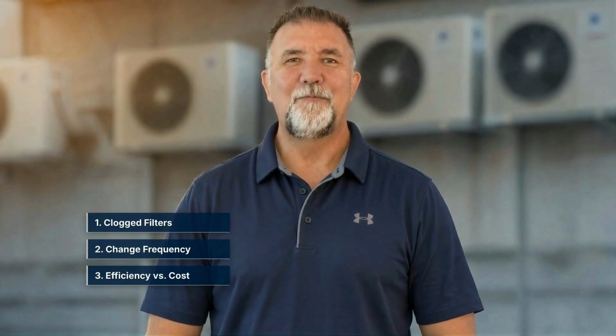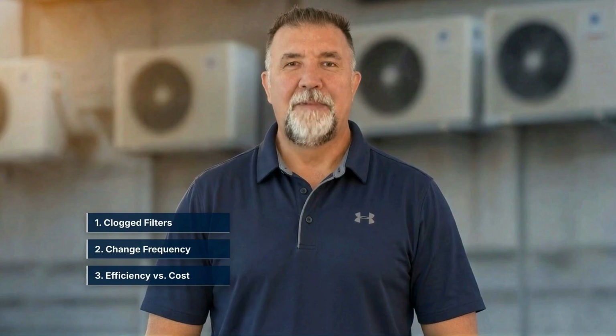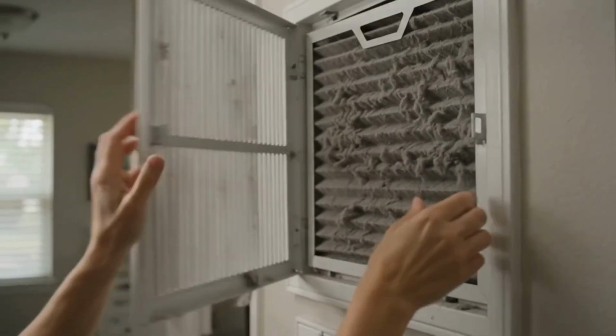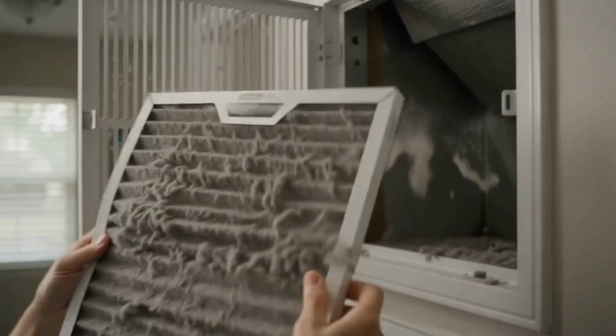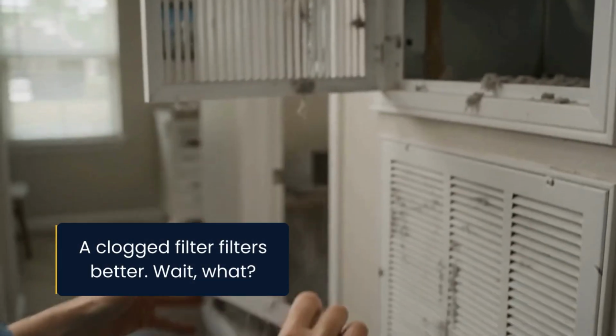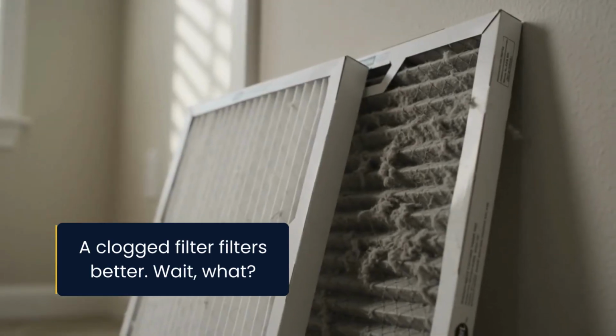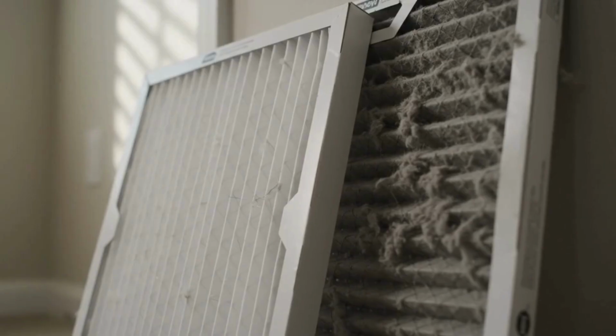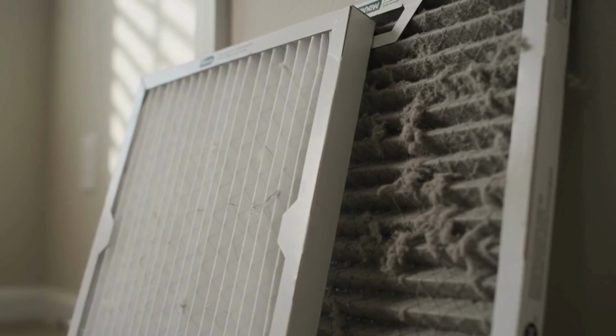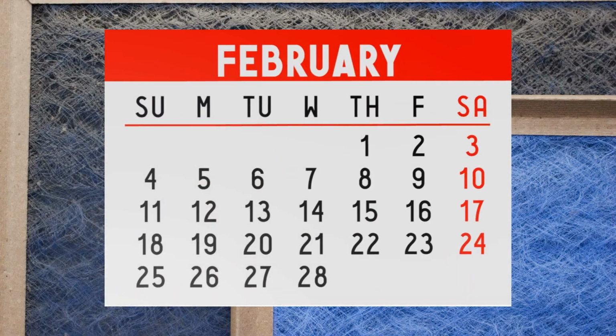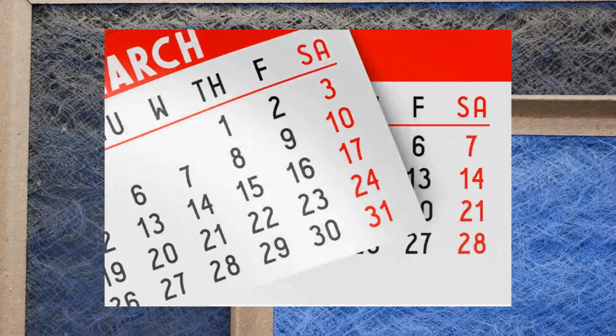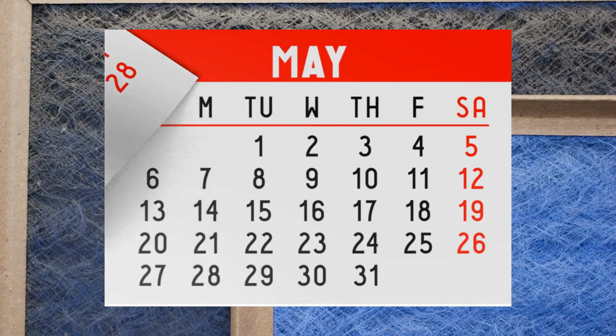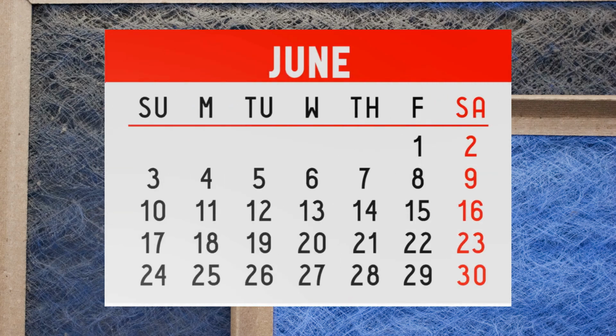But yes, there is a point, it's not a very big window, but as the particles build up on the filter, well, what happens? We restrict the filter more. And when we restrict the filter more, yes, we're going to capture more particles. But it's such a fine window, and it's going to be very difficult for you to determine if you try to go for that. But doing a good look at the filter, and if you can afford to change the filter and you look at it once a month and it doesn't look that bad, or you look at it every 2 months and it doesn't look that bad.